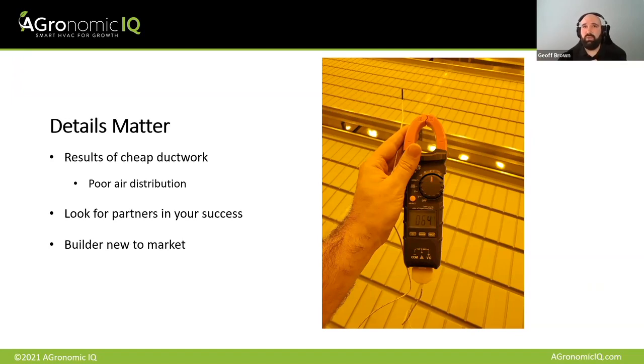And so in this room, when I took this measurement, it says 64 degrees Fahrenheit. The room was downright chilly, but the equipment was seeing an 85-degree return air temperature. So about a 20-degree spread between what the canopy is seeing and what the equipment is seeing. That's indicative of poor air distribution, poor mixing in the space. And again, that air distribution can be accomplished with good ductwork design, with air rotation fans intelligently placed.